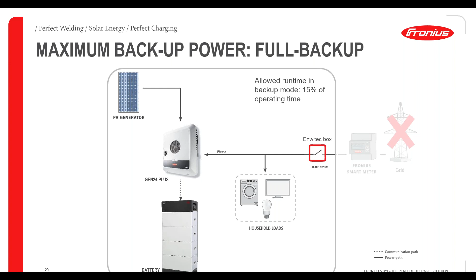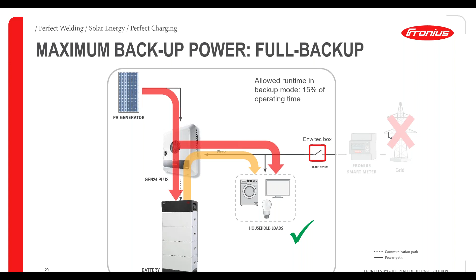It says the allowed runtime in backup mode is 15%, which means that, just as an example, if we are having the system running for 100 days and the grid is down after 100 days, you can continue using the system in full backup mode for another 15 days. And why do we say that? It's a matter of warranty. Of course, you can even continue after 15 days, but if something happens with the components in the inverter and you've been using the inverter in the full backup mode for more than 15%, then no, it's not covered under the warranty.